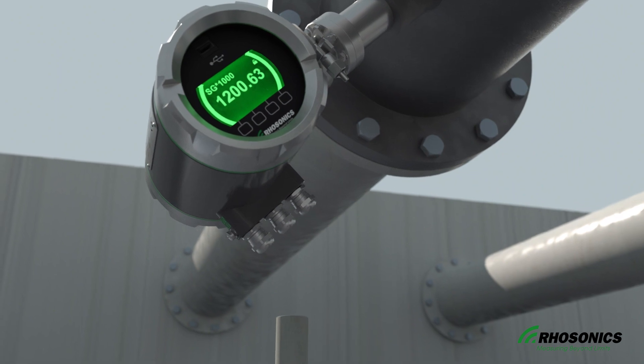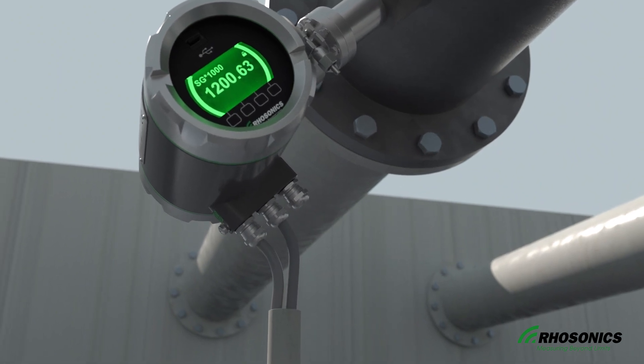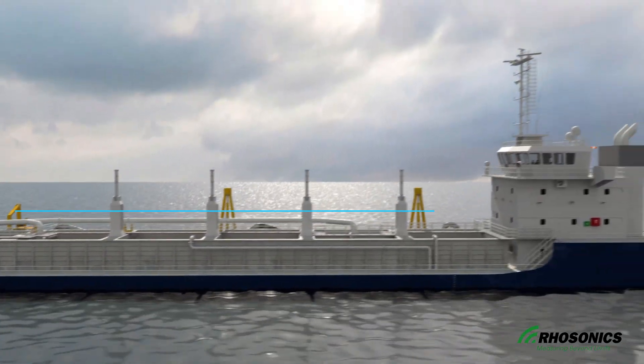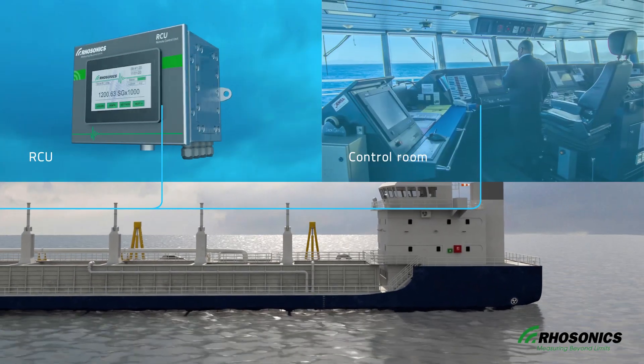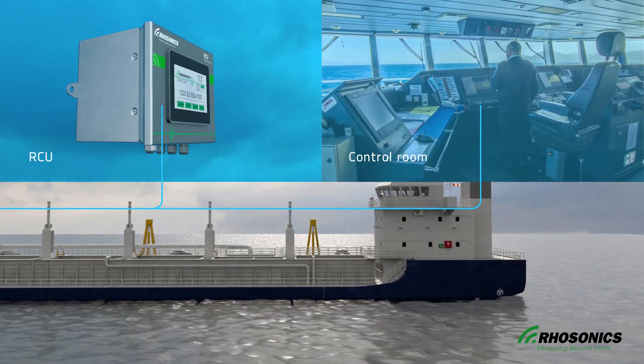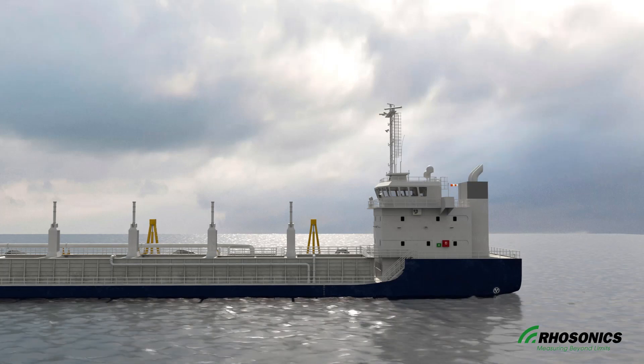After installation, the SDM is connected to the power supply and communication cable. With its connection, it can communicate directly with the DCS system through the HART protocol or through an optional RCU unit if the place of installation of the SDM is difficult to reach.